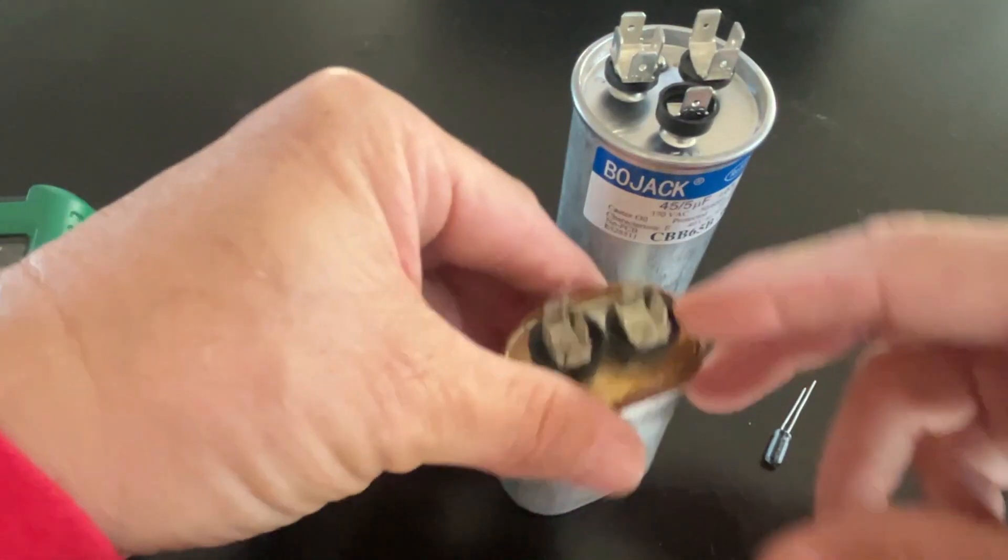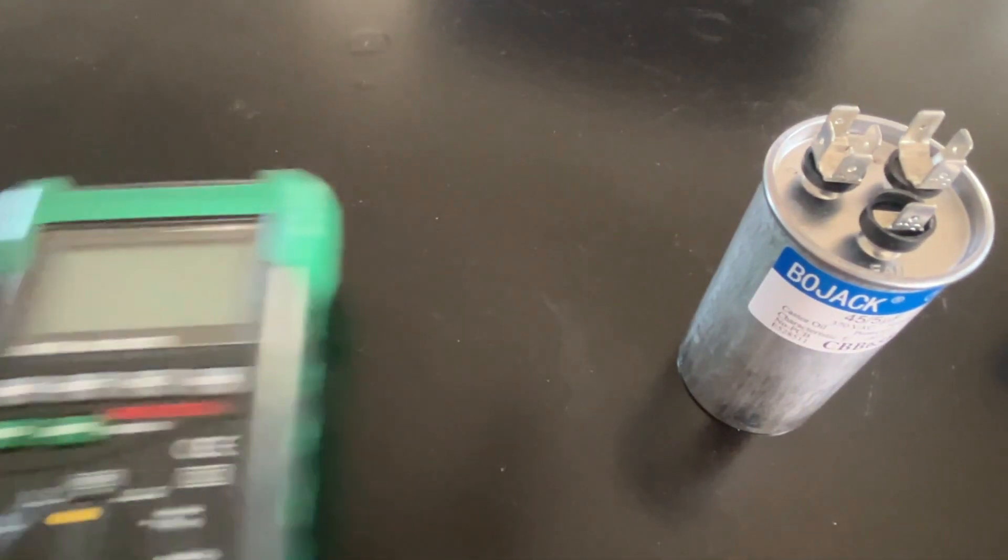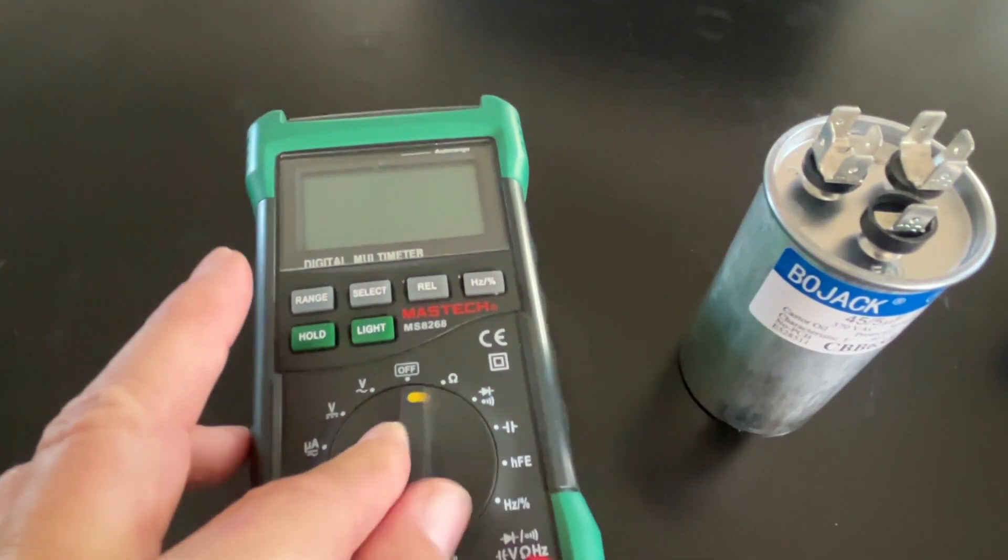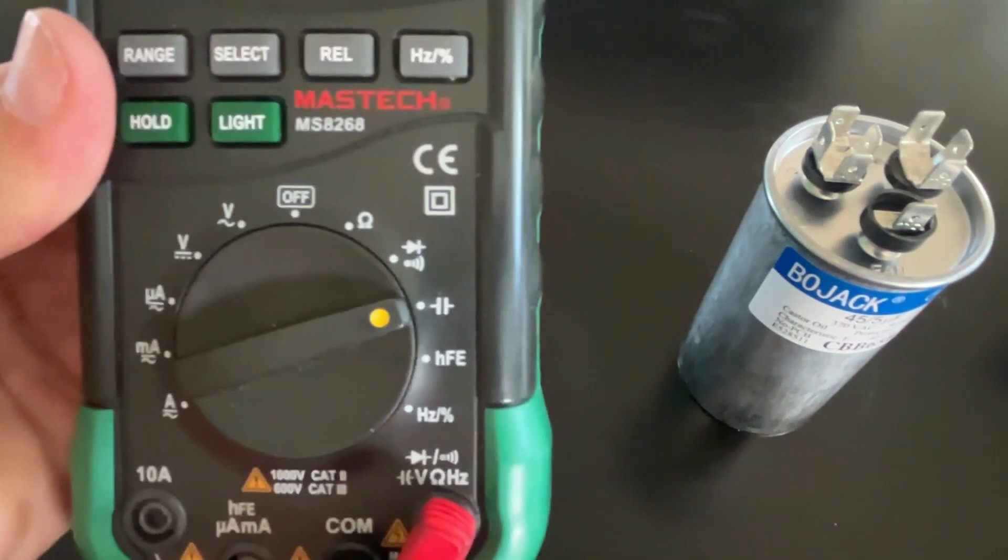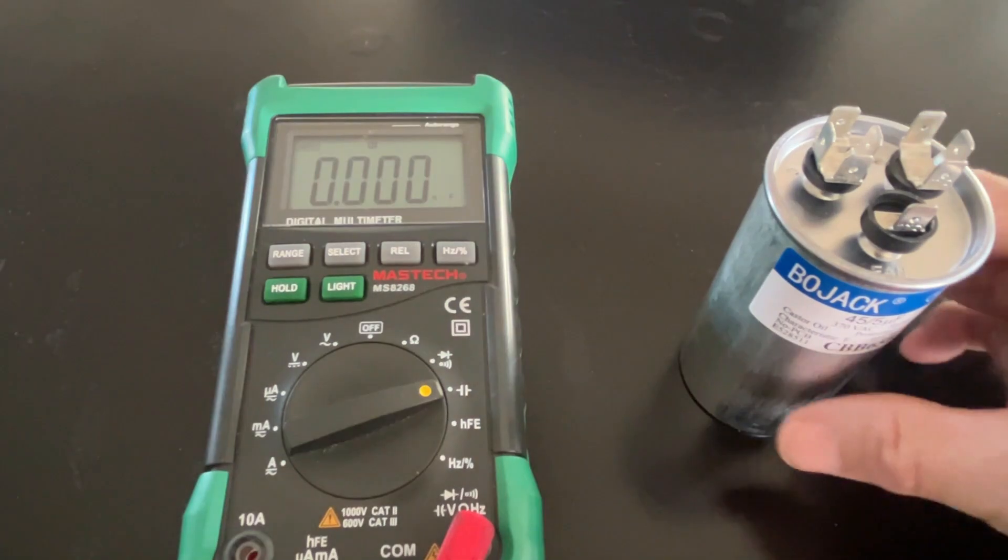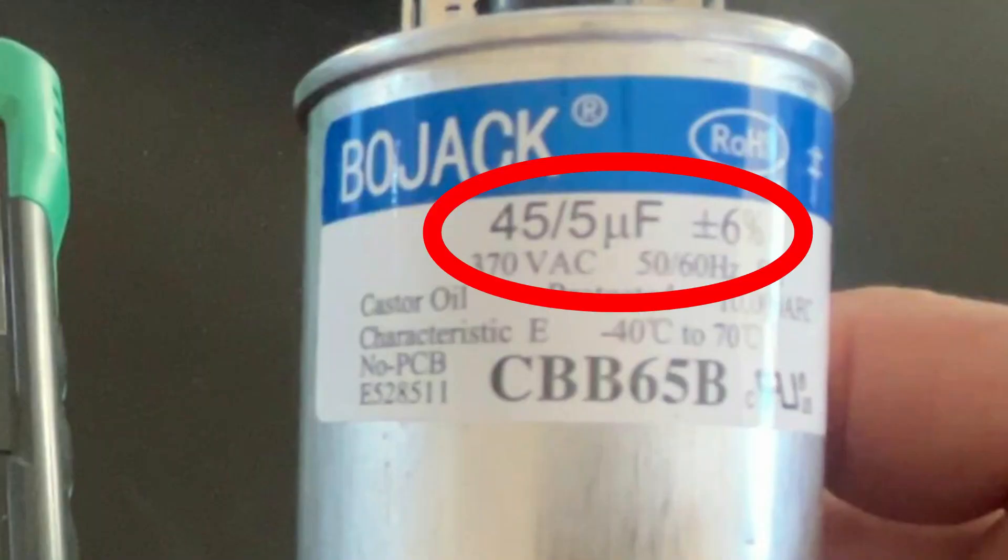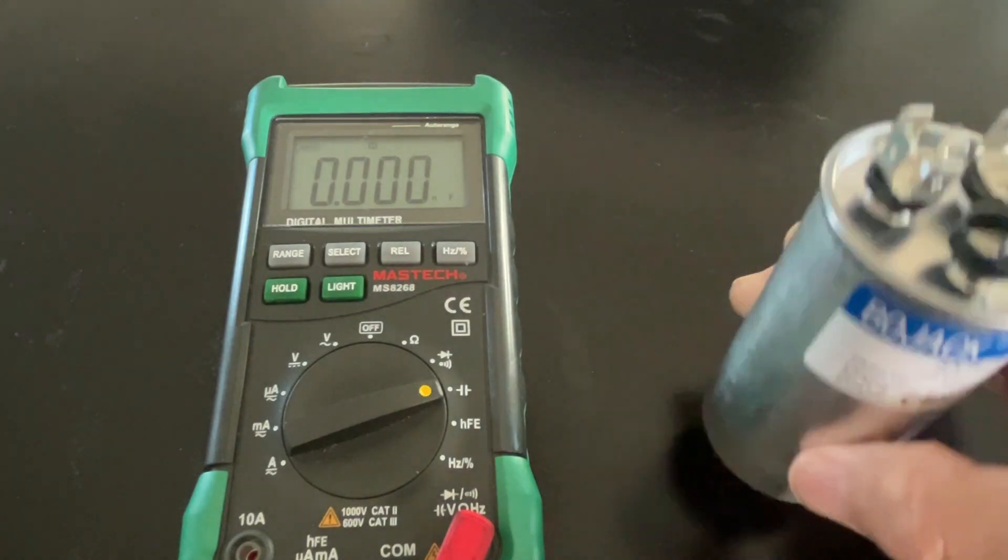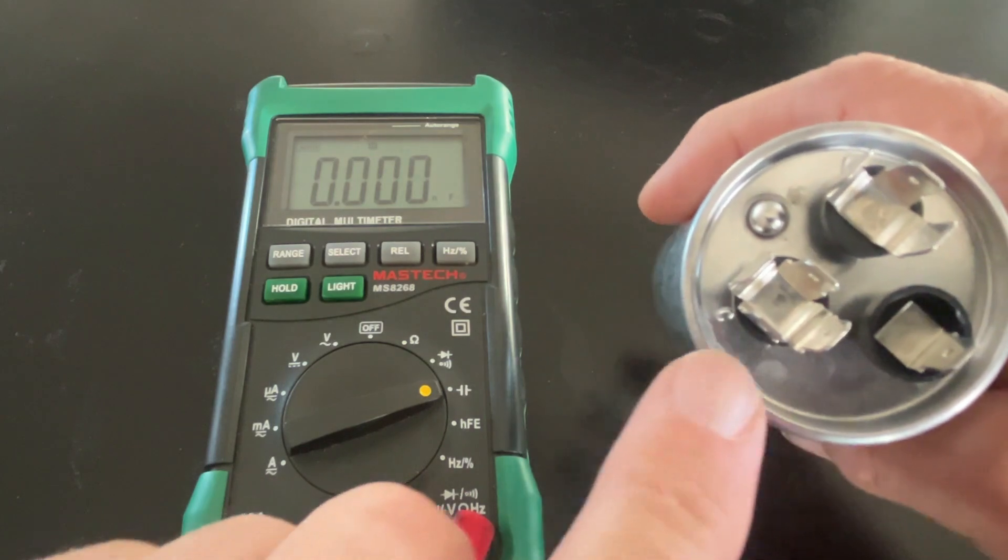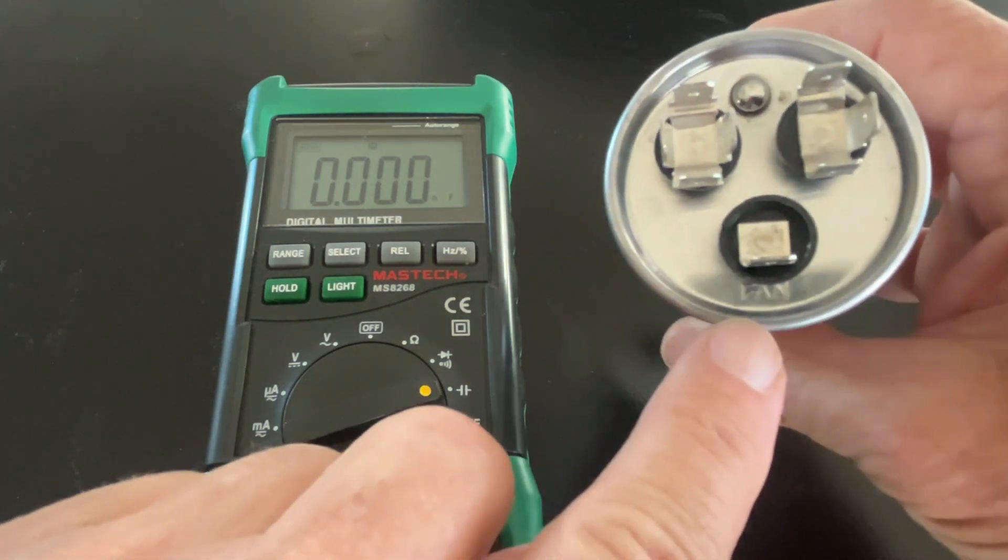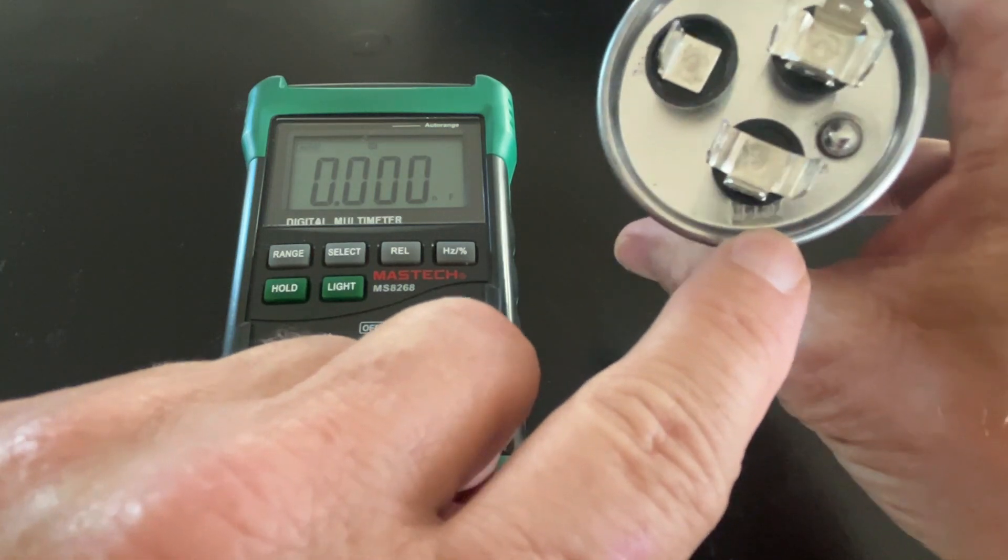All right, so let's start with this air conditioner dual run capacitor. We'll turn this to the capacitance setting right there. On this one it's a 45 by 5 microfarad plus or minus six percent, so we need to find the common.